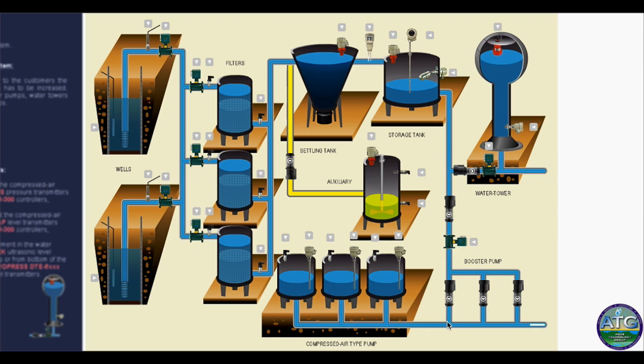And there's also another type of distribution system where we have maybe air tanks, bladder tanks, or pressure tanks they may call it. And here we have both a pressure transmitter for the pressure of the air side, and then we also may have the water level inside of that tank. So we have an instrument for each of those, and then we have the pump system going out. There we may have another pressure transmitter before it goes into the distribution system.